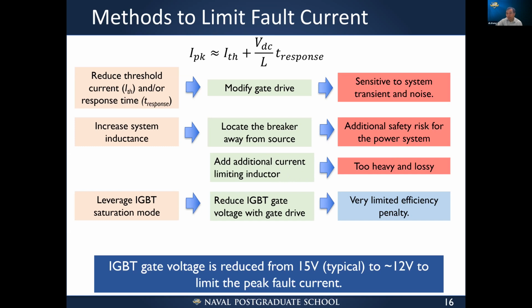For ground level applications, probably it's okay, but for aviation applications, this is just too heavy and lossy. Keep in mind, the target is 12 kilograms per pole. So the team picked to reduce the IGBT's gate voltage and leverage IGBT saturation mode to do this. Later on, you will see some efficiency penalties, but very, very limited. So we reduce the IGBT gate voltage from 15 volts typical to about 12 volts, so we can limit the fault current.